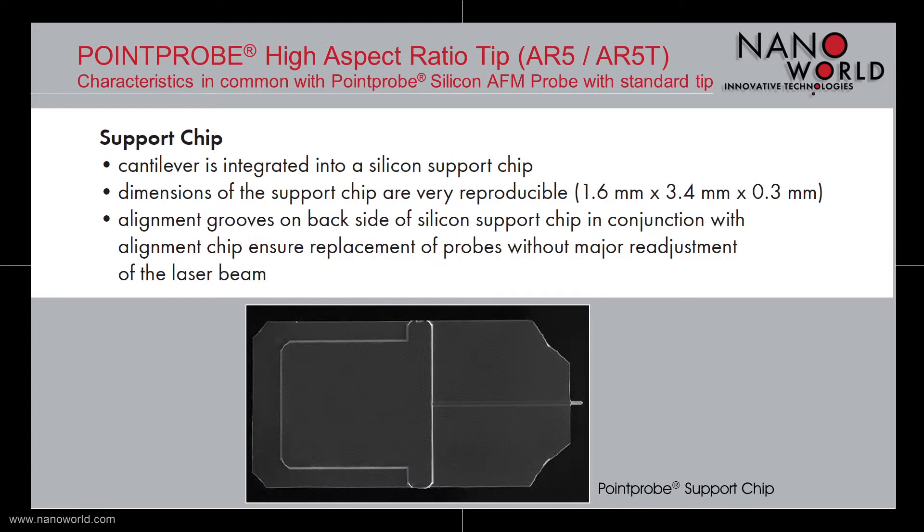The cantilevers of our Pointprobe High Aspect Ratio Tips are integrated into a silicon support chip with alignment grooves on the support chip's back side, to ensure probe replacement without major readjustment of the laser beam.